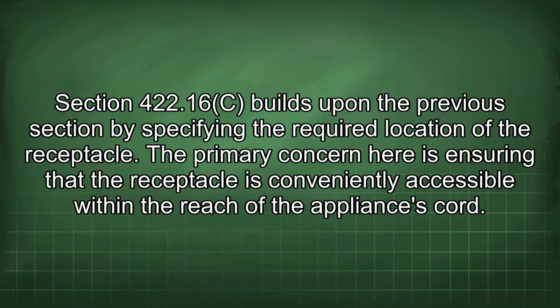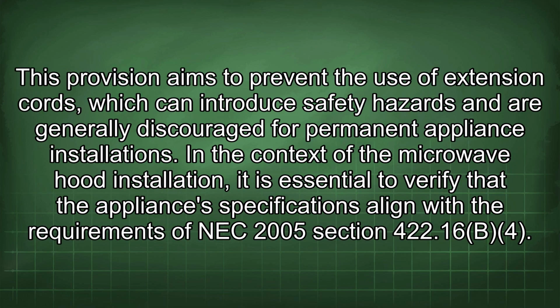Section 422.16c builds upon the previous section by specifying the required location of the receptacle. The primary concern here is ensuring that the receptacle is conveniently accessible within the reach of the appliance's cord. This provision aims to prevent the use of extension cords, which can introduce safety hazards and are generally discouraged for permanent appliance installations.